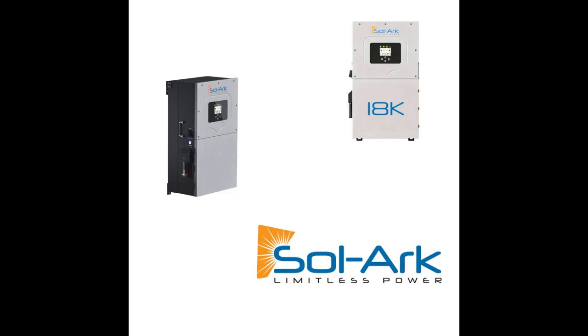And sometimes maybe your customer's goal is a time of use offset, where they want to discharge during their peak billing hours on the grid. A lot of those customers will be in California, where they have peak rates from 4 to 9 p.m., which skyrocket past 80 cents a kilowatt hour, which is ridiculous. So if you're able to discharge from a large amount of storage at that time, you're able to make a much more cost efficient system. You're really able to show the value of your system and increase the return on investment that the customer bought the system for. And they also have a layer of resiliency and extra battery to participate in other programs like virtual power plant programs. Maybe there are programs for energy efficiency upgrades that give rebates on X amount of kilowatt hours per storage.